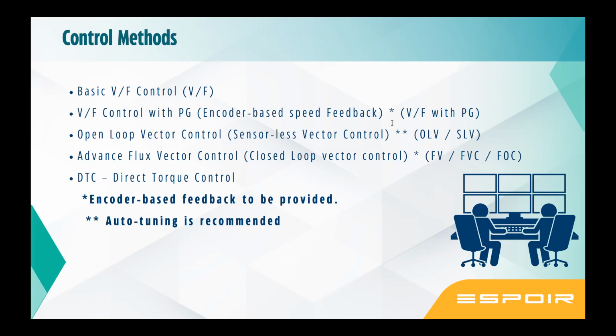There are 18 to 22 parameters which the drive will try to read by injecting certain voltage and frequency and analyzing it, and it does the mathematical modeling of a motor. Now, you may have to do this tuning 2 or 3 times.